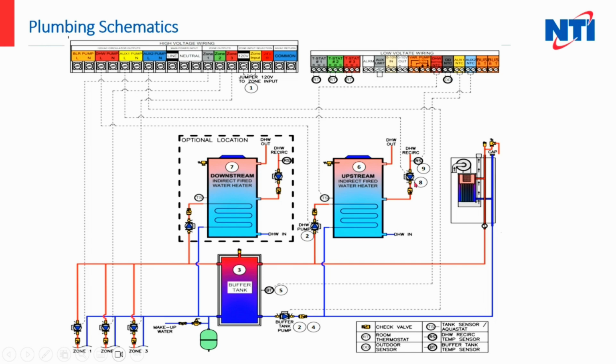Another thing shown on this diagram, and this isn't shown on the previous ones, is if you want to use domestic hot water recirculation, you can do that. You'll need to both install an auxiliary sensor, which would wire back to your aux NTC connection, and you'd have to supply a bronze or stainless pump for your domestic hot water recirc, and then this pump would wire back to the aux1 in this case. And the way the domestic recirc circulator works is when that sensor gets below a certain temperature, this pump will kick on.